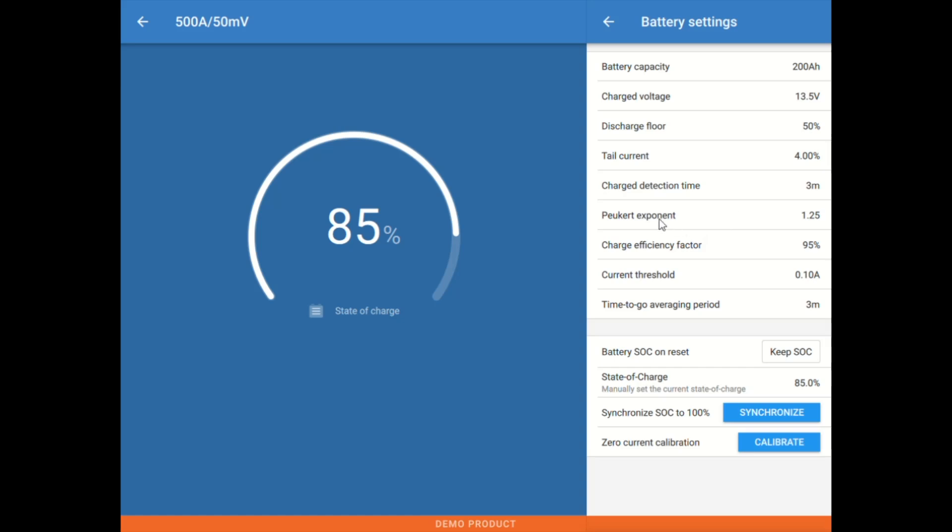Below that, we have the Peukert exponent. That essentially is or can be thought about like a discharge efficiency factor. In this case, 1.25 is most commonly used for a lead acid battery. We might go 1.20 on some gel AGM, higher efficiency lead. But we'll use 1.05 with most lithium chemistries.